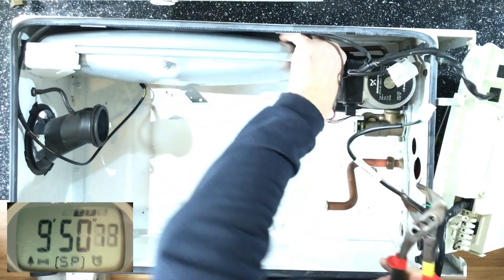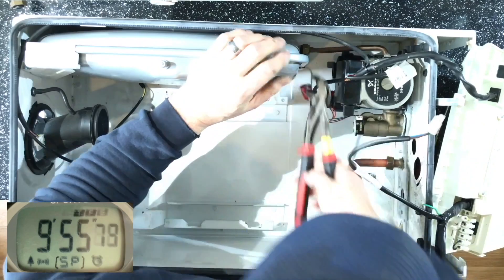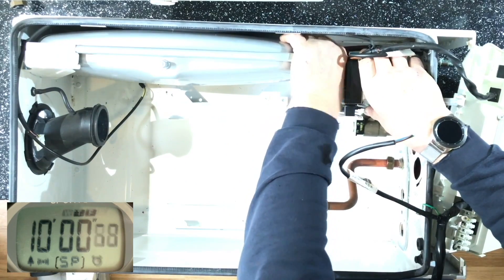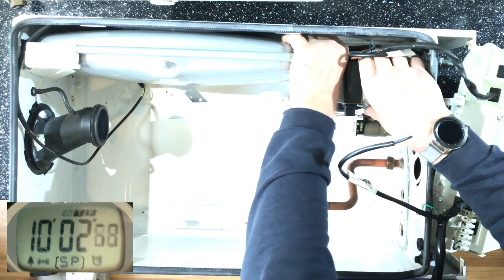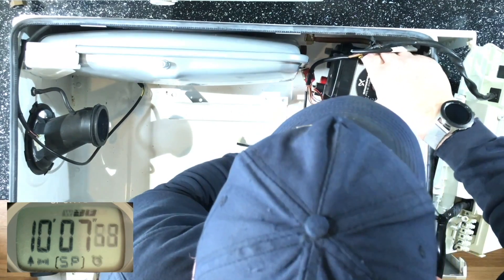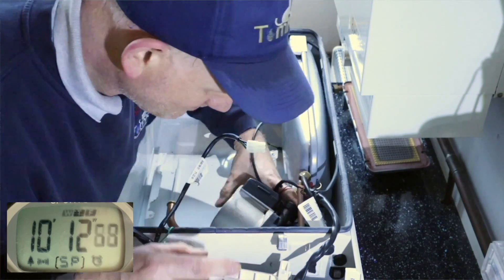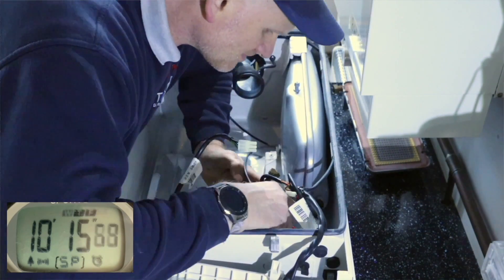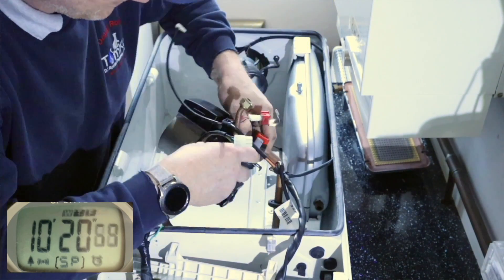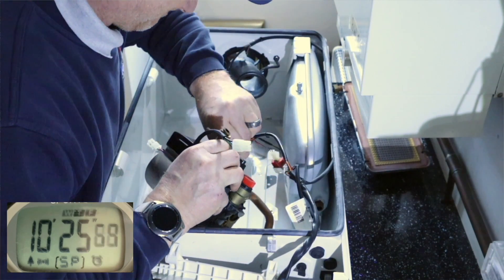So I'm just undoing this copper pipe going to the expansion vessel. Now one thing to look out when you're changing the expansion vessels on these boilers, the actual connection off the pump is different on the newer versions than it is on the older ones. So as you can see on this one, it's still a copper pipe going up to feed the expansion vessel. But on this one, it comes off the side of the pump, whereas the newer ones come off the back of the pump, so you've just got to watch out that you make sure you get the right expansion vessel.